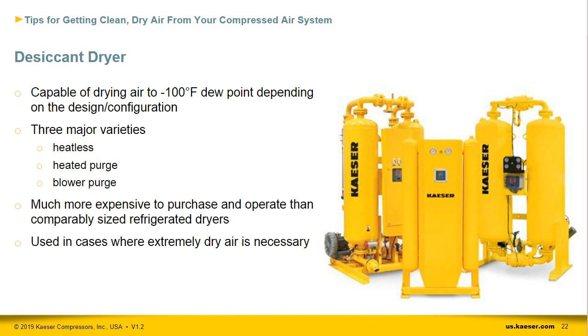They're typically used when very dry air is needed, such as for food or pharmaceutical production, painting processes, or, as needed, when piping runs outdoors or through cold environments. It's important to determine whether this level of air quality is necessary before making a purchase, otherwise the air is being overtreated at an inflated cost.